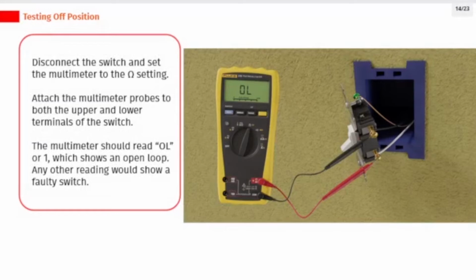Disconnect the switch and set the multimeter to the ohm setting. Attach the multimeter probes to both the upper and lower terminals of the switch. The multimeter should read OL or 1, which shows an open loop. Any other reading would show a faulty switch.